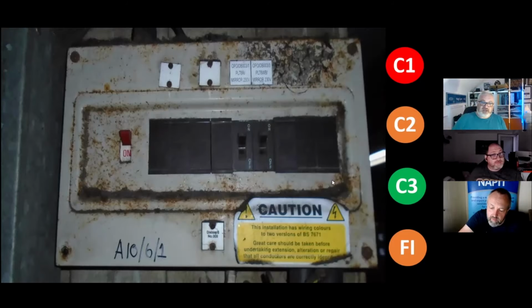Looking at the age of the breaker, looking at the level of corrosion on the surface, just based on that, I would suggest the asset is nearing the end of its life, and I would recommend improvement of it, i.e. replacement. But you'd still take the cover off?